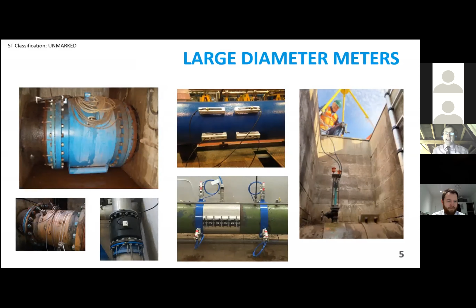There are four technologies we primarily use in the UK. Electromagnetic meters are by far the most popular meter installed in the UK water industry on larger mains. These are fairly easy to install, if - and that's a big if - you can turn off the main. So 30 or 20 years ago, when lots of these were installed, we used to write letters to the customers telling them they'd go without water for a few hours, and we would drain down the main and install an electromagnetic meter, which generally are the best meters to install.